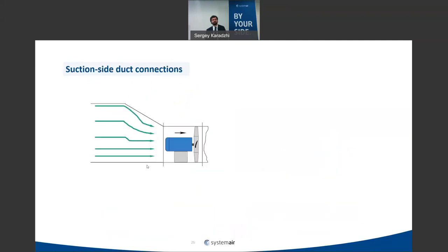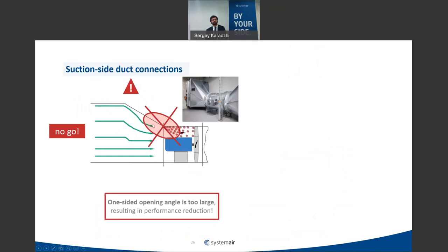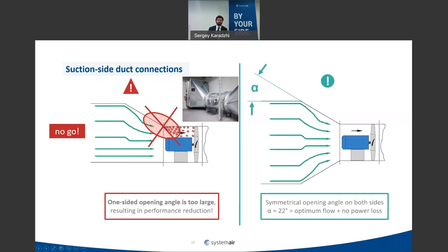A side duct connection on the inlet is also not recommended, because the angled duct creates flow separation that enters the fan, causing part of the fan to operate in a separation zone — which, as mentioned, can even lead to fan destruction. Always use a symmetric opening angle. On the inlet side, you can use larger angles than on the outlet because you have a confuser — the velocity is increasing — and the optimum angle according to technical references is around 22 degrees.